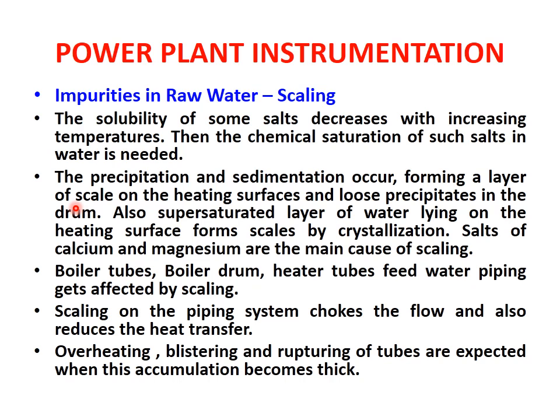Therefore due to the presence of salts, the scale formation will take place due to the chemical saturation of the salts. Due to that, the inside part of the boiler will be exposed to precipitation and sedimentation. So in this case, they will form a layer of scale on heating surfaces and loose precipitates in the drum.